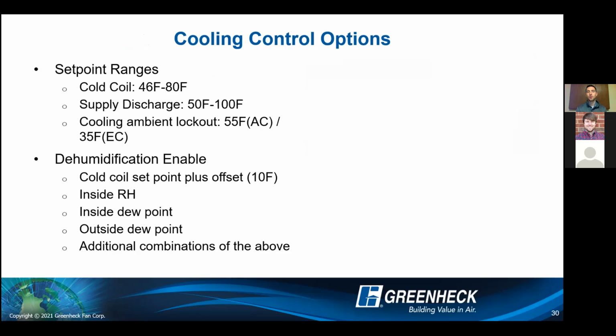But related to controls, I want to touch on some set point ranges that we have on our controllers, specifically related to more DX situations. So first off, I want to talk about the cold coil. The cold coil can be set anywhere from 46 degrees up to 80 degrees. So I believe there was one question about low dew point type applications. The way that we are configured and set up and based on our factory testing, 46 degrees off that cooling coil is the minimum that we will go during dehumidification.